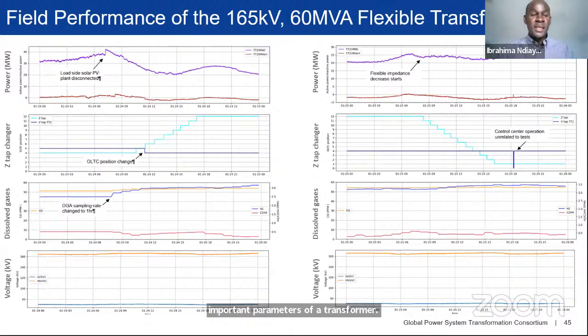And as you can see, when we started to change the tap changer of the transformer from the low value to the high value using a staircase, you can see, compared to the right side figure, that we were aggressively dropping the power through the line, through the transformer. We are not showing here the natural load flow on a daily basis through this power transformer, but you can sense how aggressively the power was dropping.